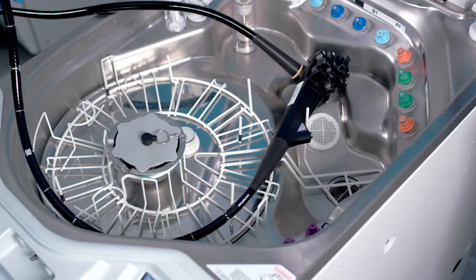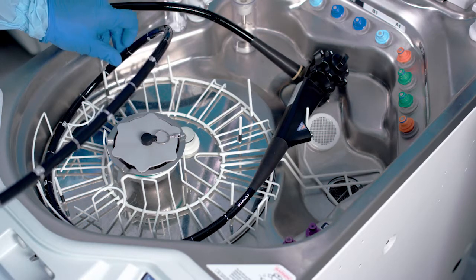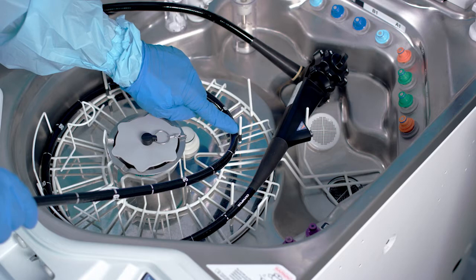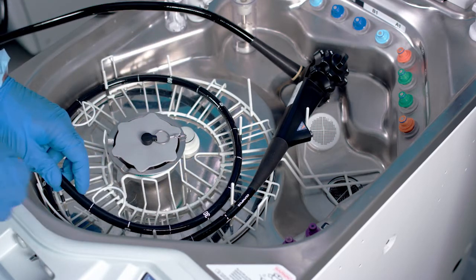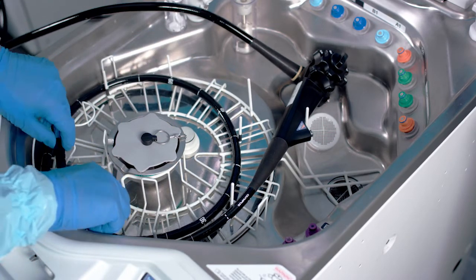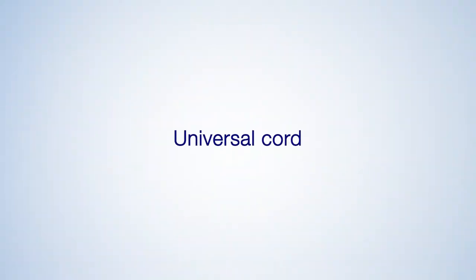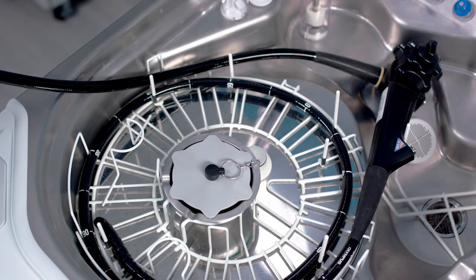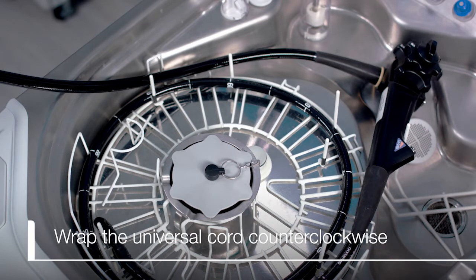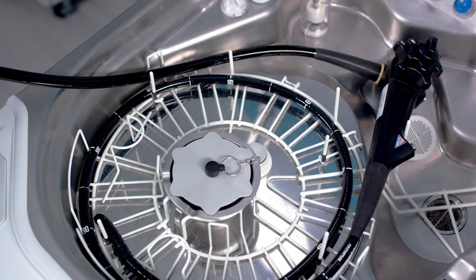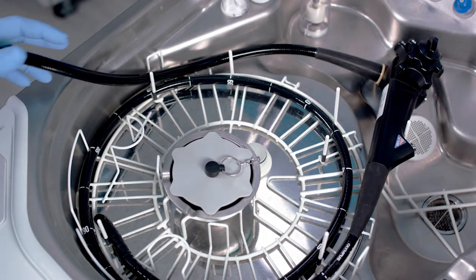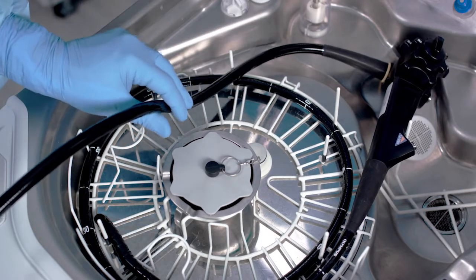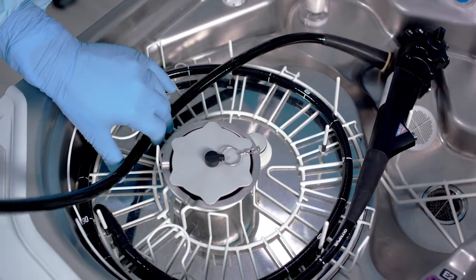Then, we're going to wrap the insertion tube clockwise around the retaining rack from the outside of the retaining rack moving toward the inside. Make sure that the insertion tube's distal end is placed within the retaining rack. Once the insertion tube and the control body are successfully loaded, it's time to wrap the universal cord counterclockwise inside the retaining rack. Remember to start by wrapping it to the right side of the retaining rack pin. Place the universal cord under the hook of the retaining rack.